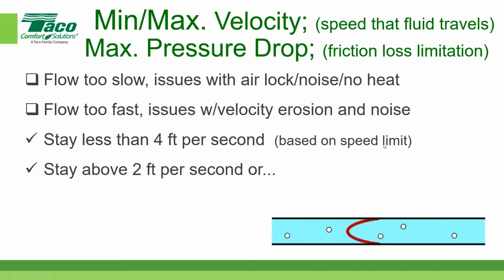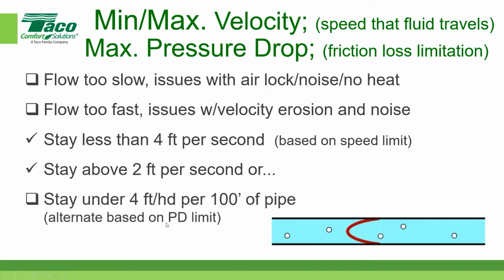Remember, that's based on how fast the water is moving through the pipe itself. So we'll look at that as a speed limit. There's another rule out there that ASHRAE talks about, and most of the people that deal with mechanical engineering firms just use this number because it works both ways for them. The 4 foot and the 2 foot comes from Modern Hydronics and from Siegenthaler and people that prescribe it up to about 1.5 inches. And then from 2 inch and bigger, they say, and I'll show you why in a second, let's just use the 4 feet of head per 100 feet of pipe. And that works well. Let me explain what this means, because sometimes it doesn't make sense to everybody.